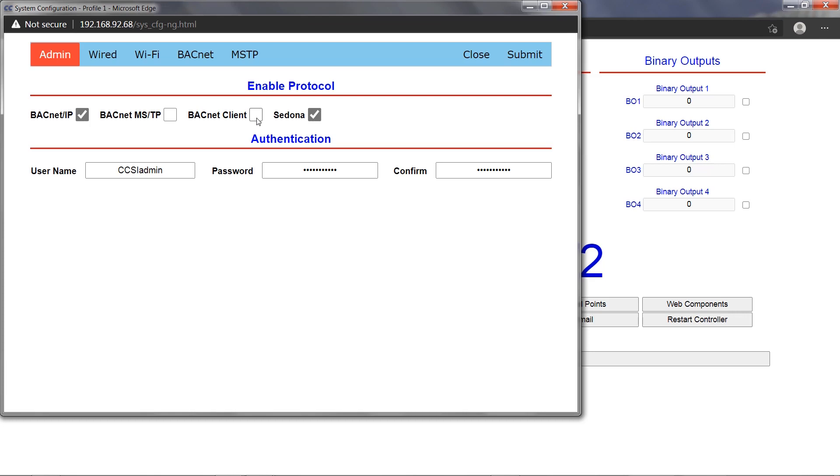The BACnet client checkmark enables or disables BACnet client operation. This setting is disabled by default. If enabled with BACnet IP driver enabled, the BASpi Edge operates as a BACnet IP client and server. If enabled with BACnet MSTP driver enabled, the BASpi Edge operates as a BACnet MSTP client and server.